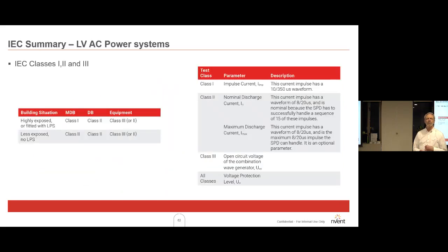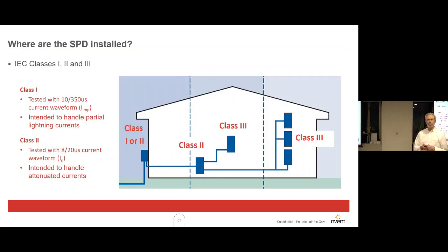There is a table in the standard which recommends that for the point of entry you should use a 100 kA rated surge diverter. At the distribution board you should use 40 kA, as stated in the standard, although a lot of suppliers, including us, have 50 kA as their standard size now. This is a 50 kA or 50,000 amp device, not particularly large, and it clips on the DIN rail. If I unclip it, there's a replaceable module with a status indicator so that you can see if it's been consumed. Because this is a metal oxide varistor, it does get consumed as it conducts surge current.